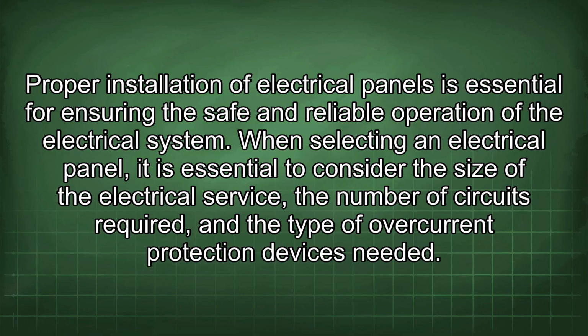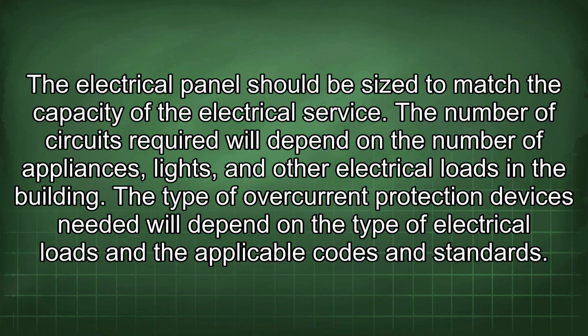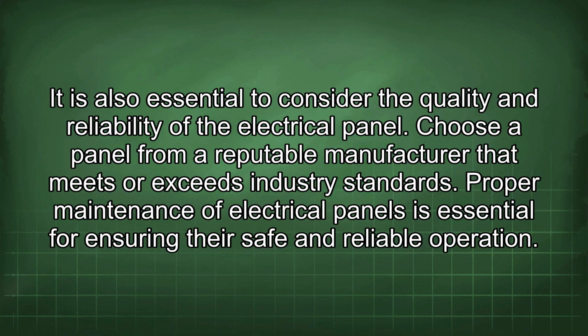When selecting an electrical panel, it is essential to consider the size of the electrical service, the number of circuits required, and the type of overcurrent protection devices needed. The electrical panel should be sized to match the capacity of the electrical service. The number of circuits required will depend on the number of appliances, lights, and other electrical loads in the building. The type of overcurrent protection devices needed will depend on the type of electrical loads and the applicable codes and standards. It is also essential to consider the quality and reliability of the electrical panel. Choose a panel from a reputable manufacturer that meets or exceeds industry standards.